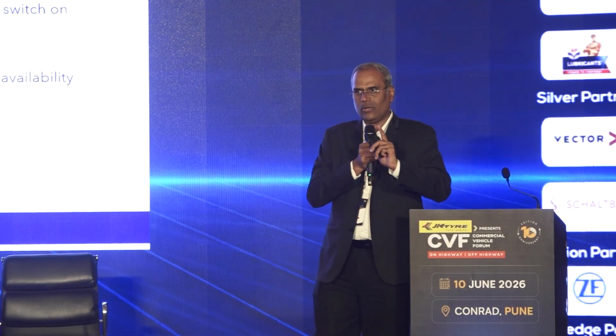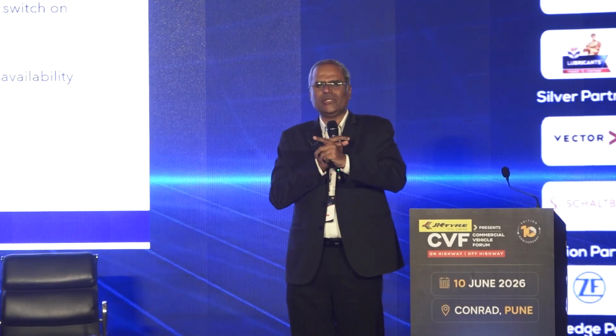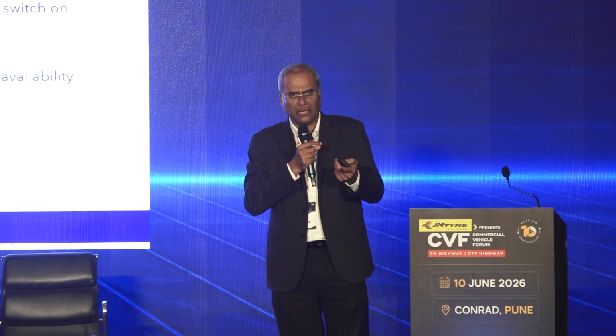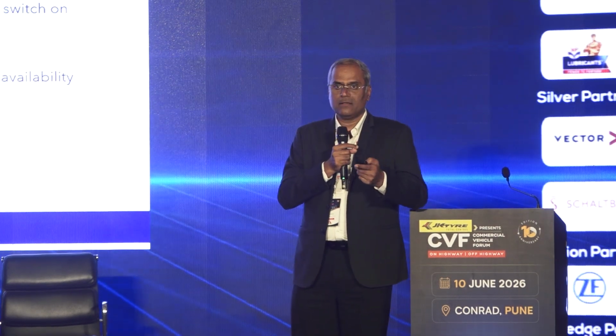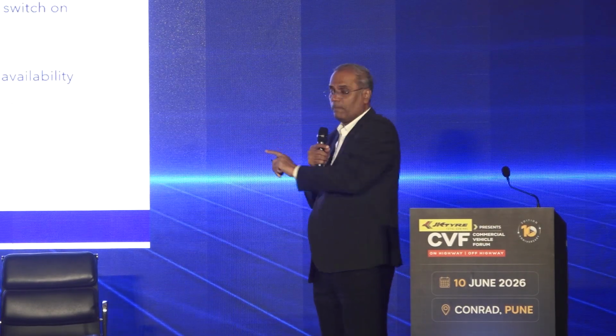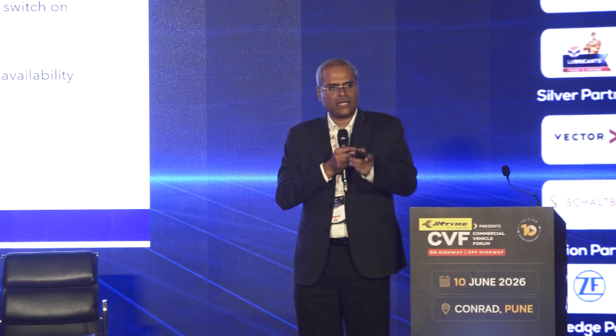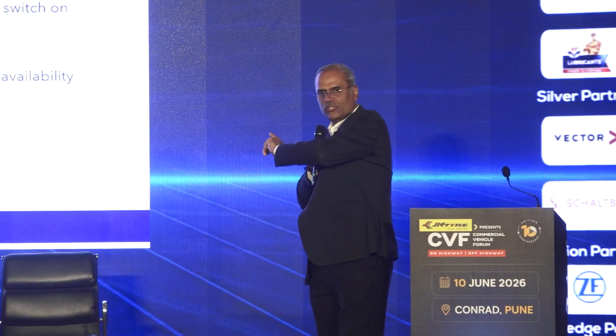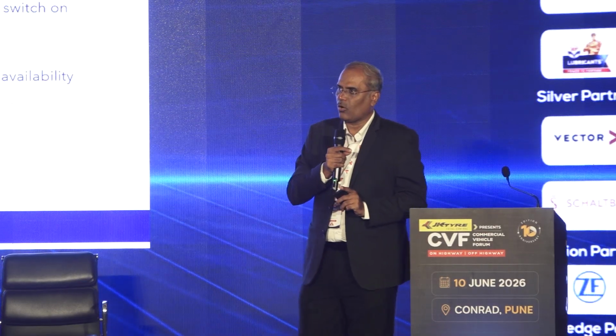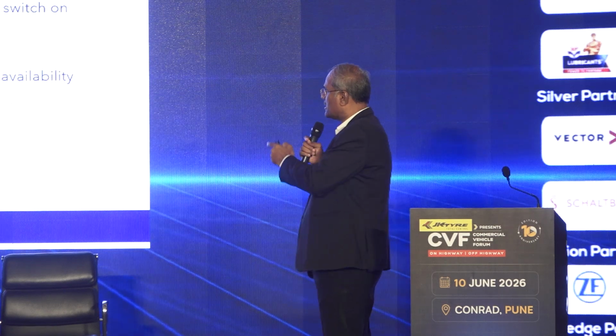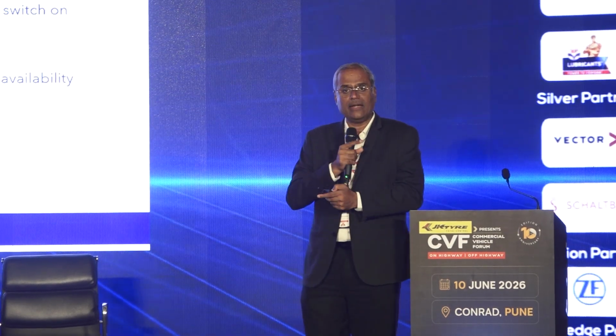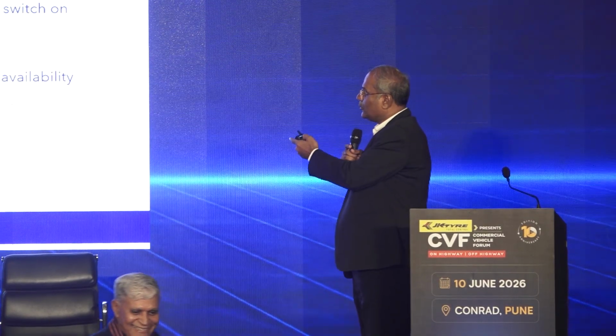The third is the higher switching current. In the normal case, you will switch the regular rated current, which could be 100 amps, 200 amps, 300 amps. But when you switch on, there is a surge because your motor is going to draw a very high inrush current. Today, your inverters primarily manage that, but in an abnormal situation the inverter would see the full load current, and these air insulated contactors can withstand it. A gas insulated contactor cannot handle a current higher than the rated current. They will actually burst. So that's the second important element of handling abnormal conditions safely. Whether it's in your battery system or in your PDU, it manages this.